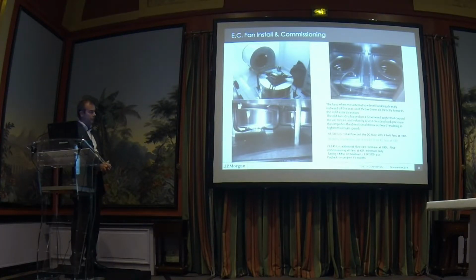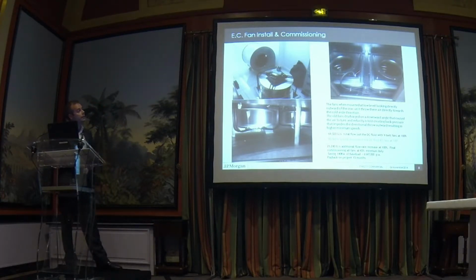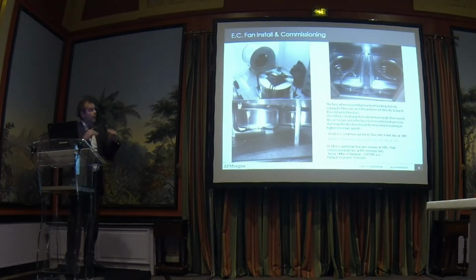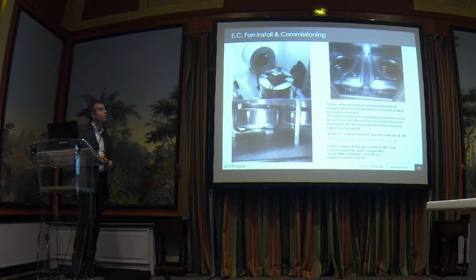There's a lot of consideration when you put these fans in. They can't sit too close together. You get a propeller effect of the air being bashed against each other. Bit of trial and error, getting the right plates, and you've got to make sure the plates are thick and heavy and strong so it doesn't get a resonance and get a vibration in them as well.